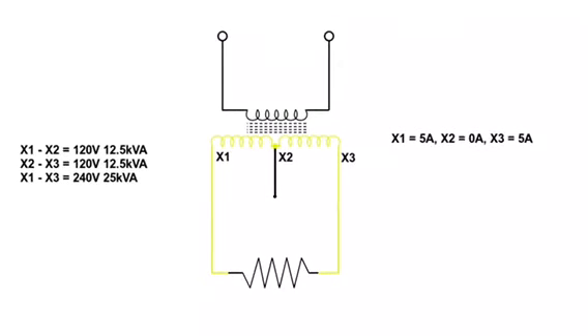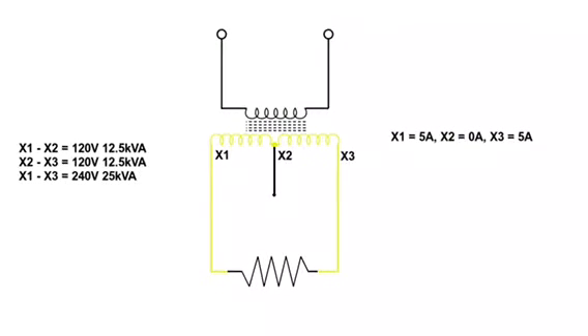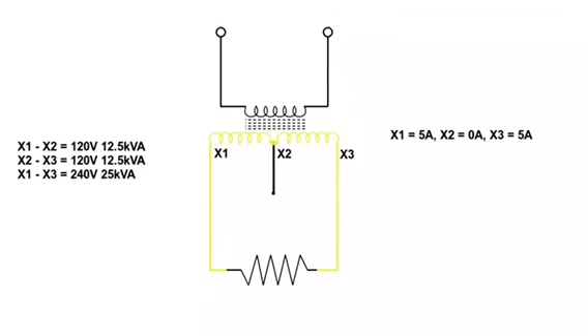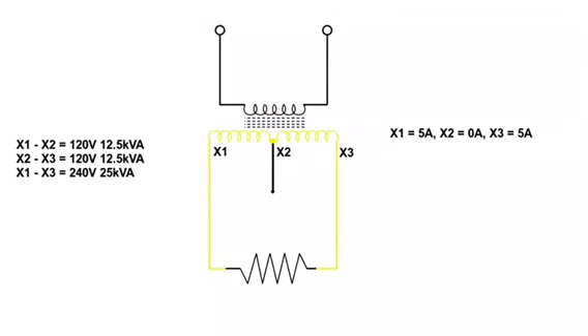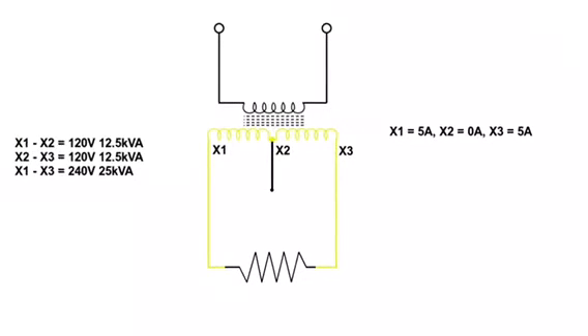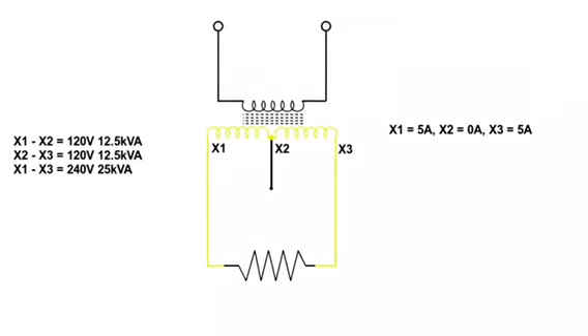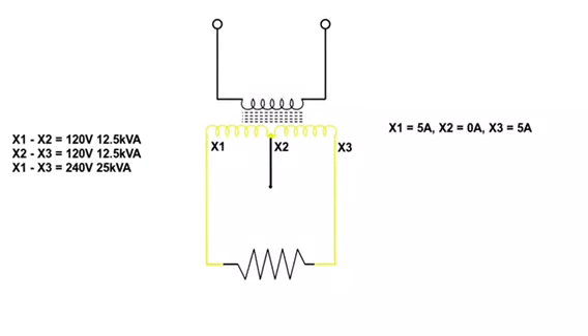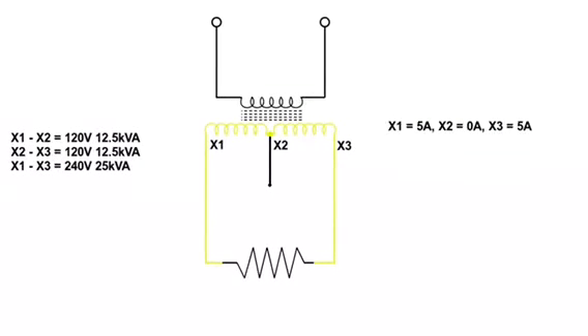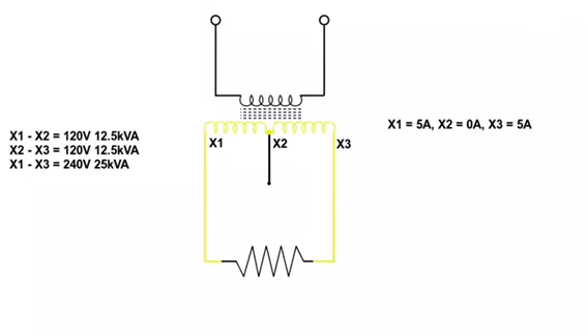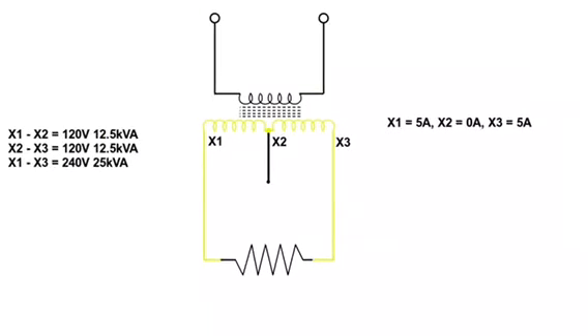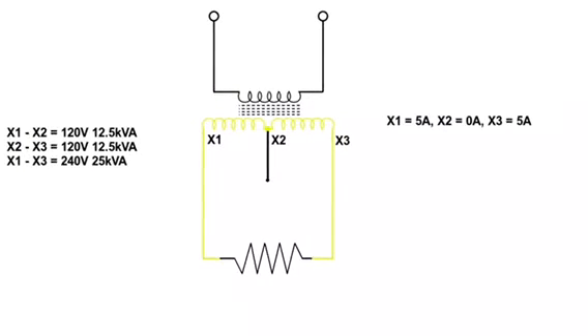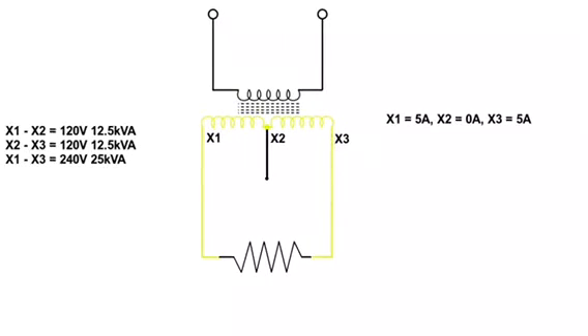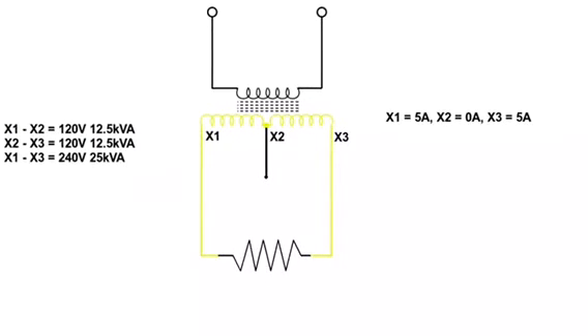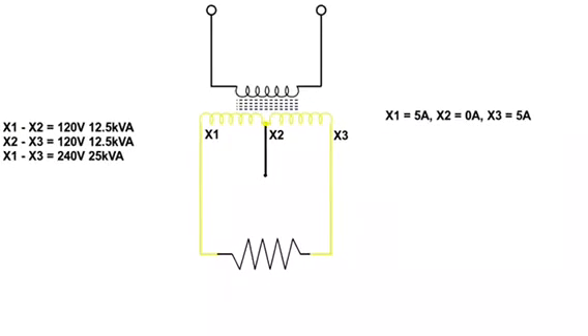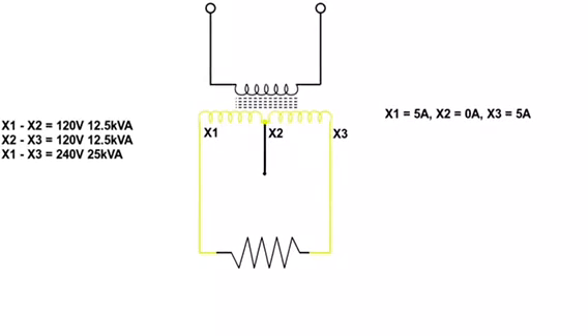Here I've removed the 120 volt loads from both X1 and X3 to neutral, and I have placed a 240 volt load across X1 to X3. To the transformer and the electrical system, this load appears exactly the same as the two 120 volt loads. So if we take our amp probe and go to X1, we'll read 5 amps. If we go to X2, we will read 0 amps, as you can see, nothing's connected to it. And if we move it over to X3, we will read 5 amps.